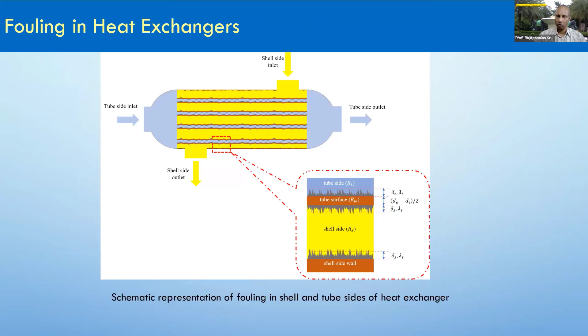We developed a simple graph paper of sorts where a company can take measurements, not necessarily continuous. They can go once a week to the heat exchangers, take pressure drop and temperature measurements, plot it on this special graph paper, and find out if the exchanger is operating in a clean zone or in what we call an alert region, where efficiency has degraded.